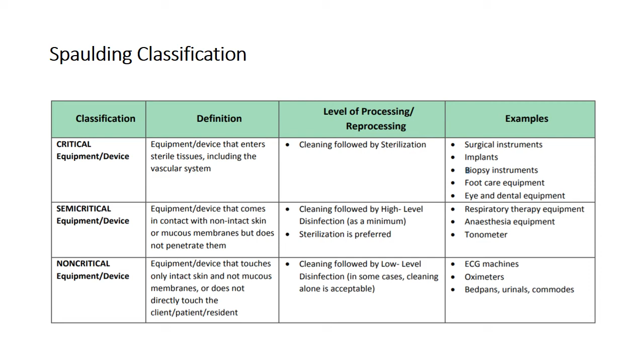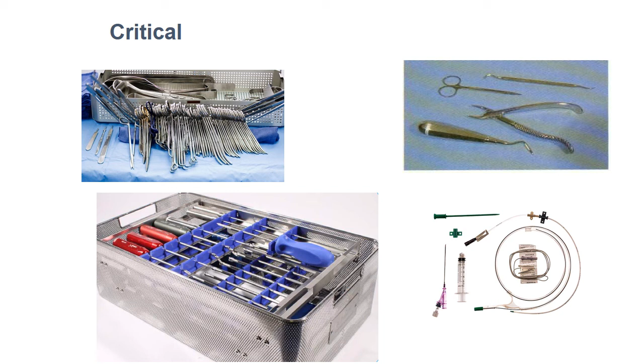Number 1, processing critical instruments. Instruments which penetrate or enter normally sterile tissue or spaces, including the vascular system, are considered critical instruments. Surgical instruments like elevators, bone files, forceps, and central lines are some examples. So they must always be sterilized between uses or may be used as a single disposable device only. Our goal here is sterility, as these devices enter the body, and they should be devoid of all microbial life including spores.